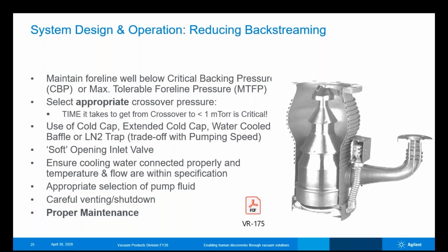And finally, proper maintenance. One of my favorite customers to go to is the maintenance guys that keep really good records on these diffusion pumps. They've characterized them, let's say at the start or installation, or when they've done a maintenance, and they can track the behavior of it. That allows them to schedule regular maintenance and appropriately schedule their downtime, and really try and avoid unplanned downtime, which of course is a real problem for our industrial customers.